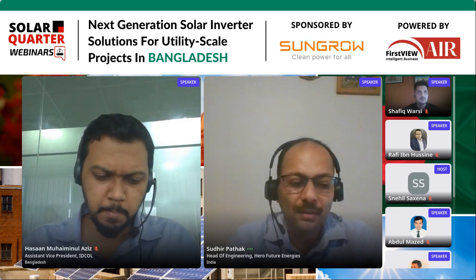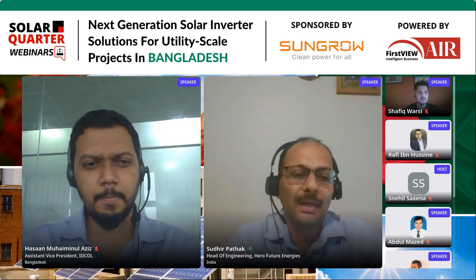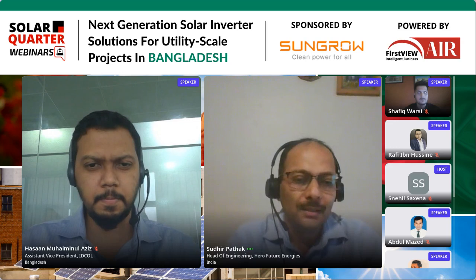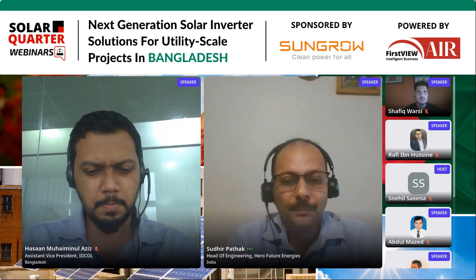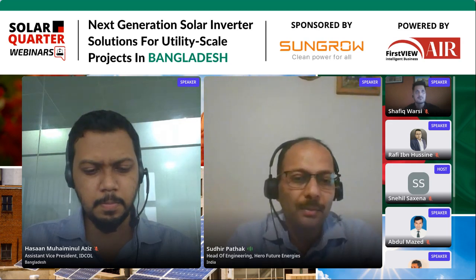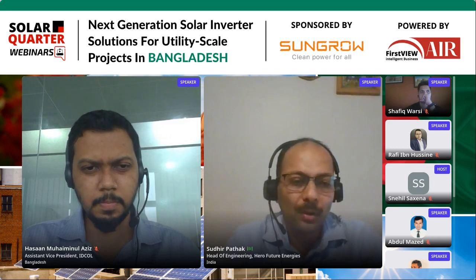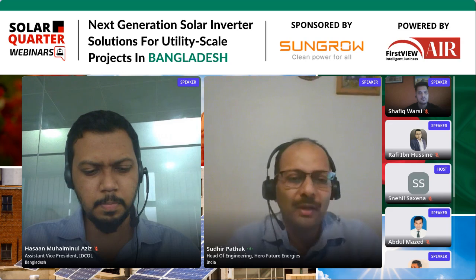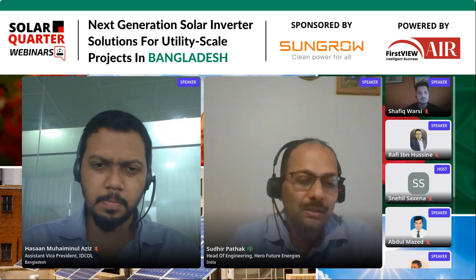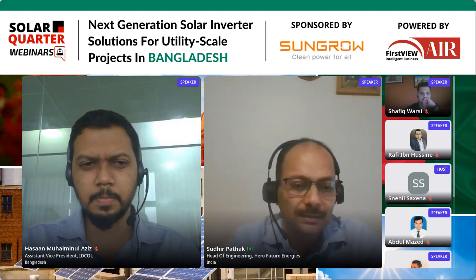The problem with SMBs is something India has learned, and I think Bangladesh is slightly behind on that, because solar is new to them. So central inverters are good if people are looking at the cost. But if you have to monitor, as you go to a 200 megawatt size plant or even higher, you can't deploy numerous people at site to keep checking with their multimeters what current is going, which string has failed. That was good for 5 megawatt, 10 megawatt, 20 megawatt. But if you go for such a big size, you need smart people, smart systems, you need IoT, right?